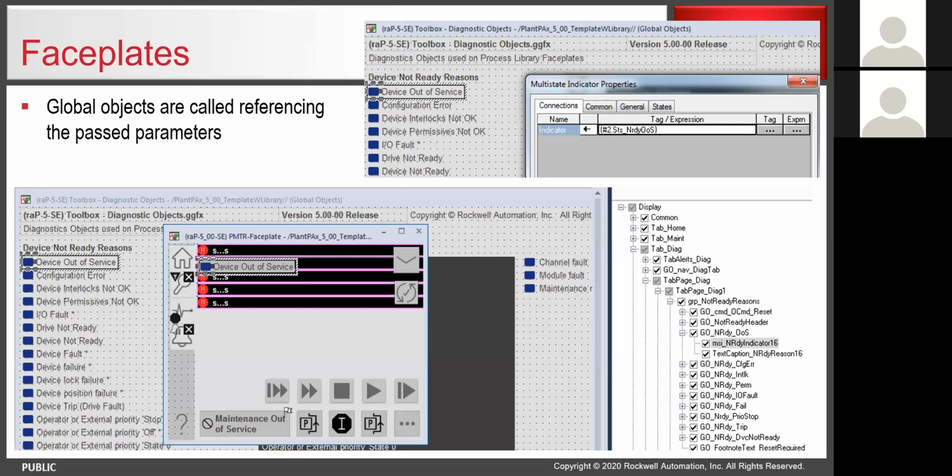So we typically look at security as more of an HMI function than a controller function. But there are also additional pieces you can do within these displays, where you can map pieces in from the controller to gray out buttons that aren't available. You can put an image of a button underneath the actual button and make the button disappear if you're not supposed to hit it, if you're in the wrong mode or something like that. So you can see that it's grayed out and it looks like it should be there, but it isn't working.